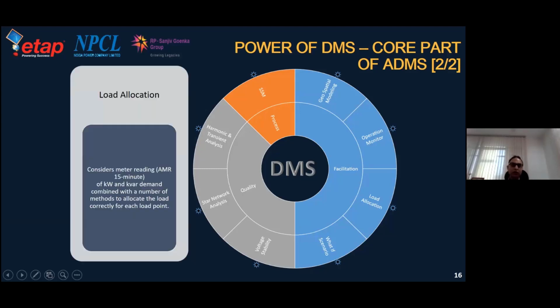Load allocation considers the meter data available at a time granularity of 15 minutes and 30 minutes, and based on that, it does the load allocation for all points where the actual quantum of load data is not available. After doing the load allocation, we can run the load flow studies, which give results almost equivalent to when the actual load data is available.